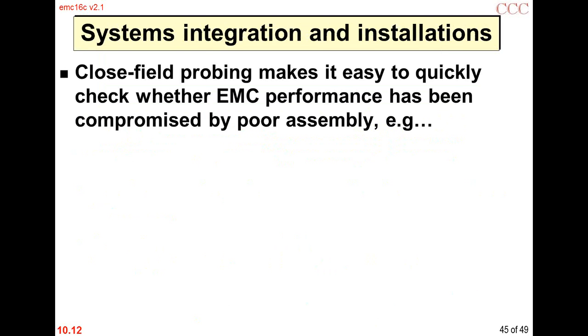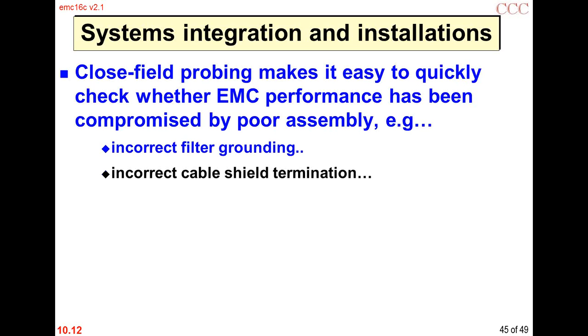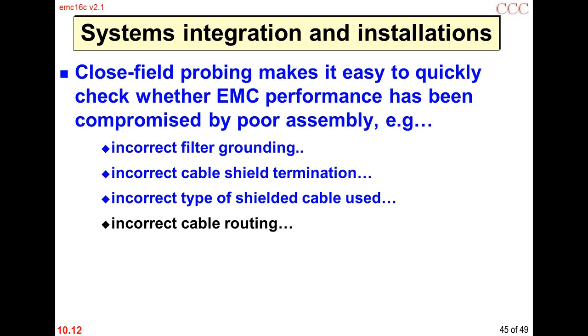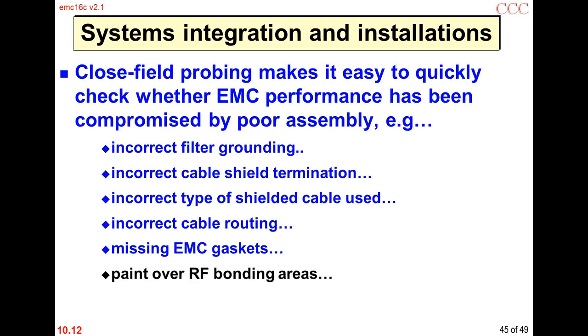In systems integration and installation, we can check whether EMC performance has been compromised by poor assembly - for instance, incorrect filter grounding, incorrect cable shield termination, incorrect types of shielded cables, incorrect routing of cables, missing or badly assembled gaskets, paint over radio frequency bonding areas, or some kind of polymer passivation, fixings not done up tight enough or too tight, and so on.